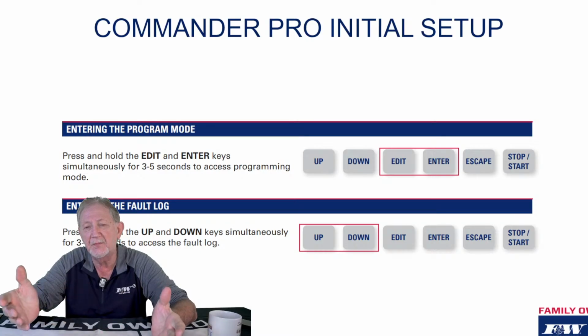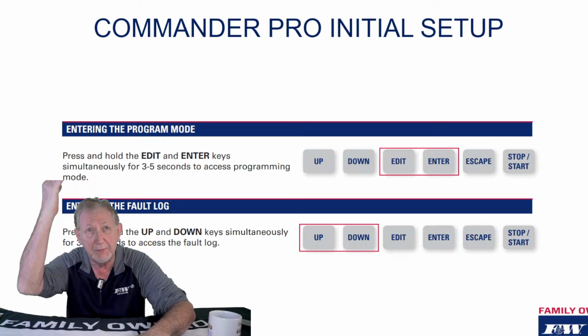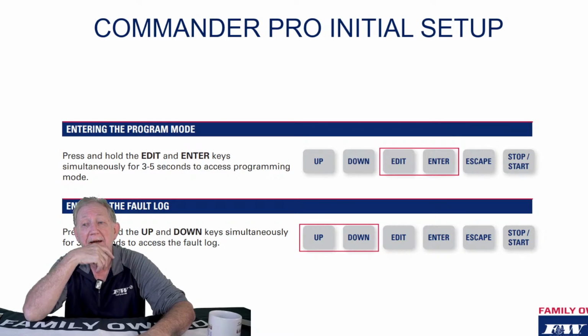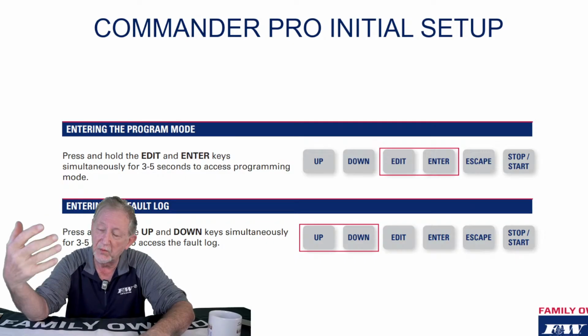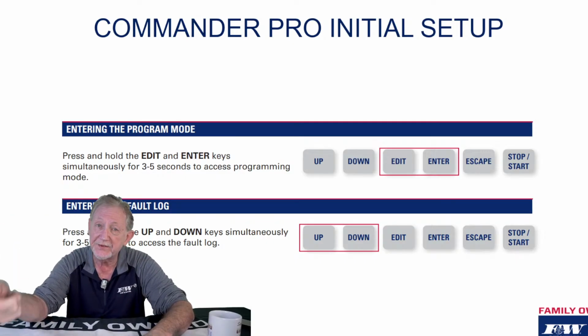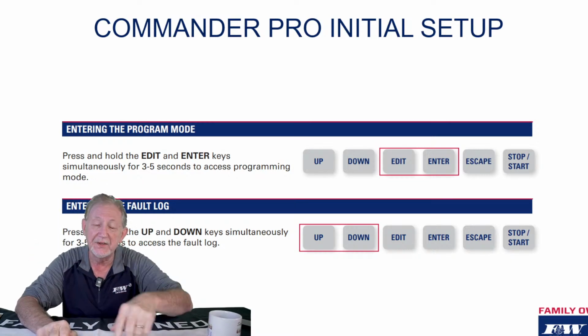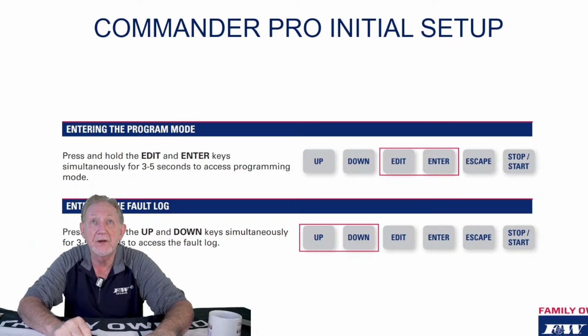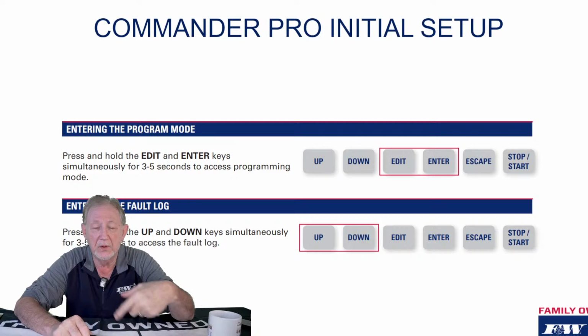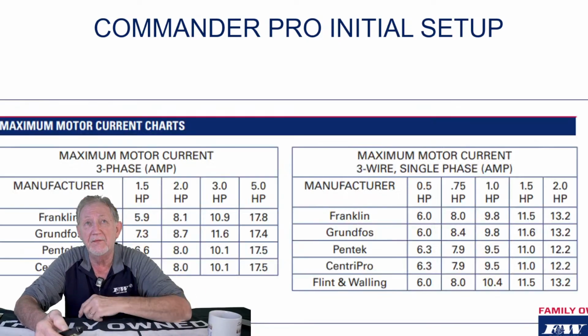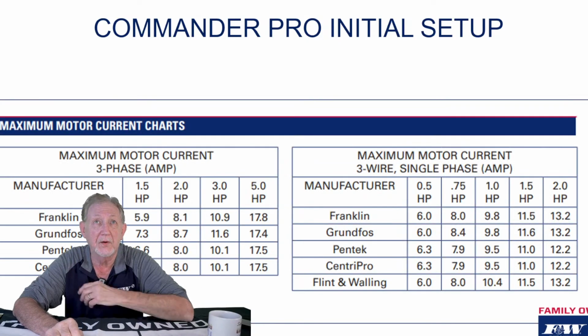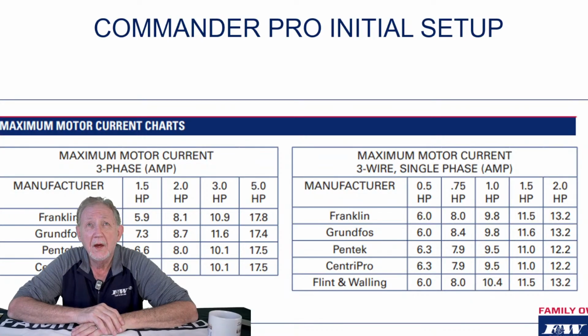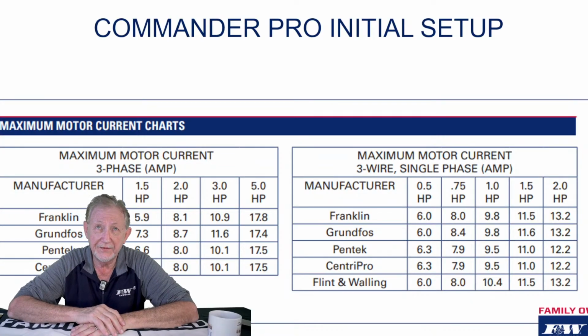So for example, if by chance you filled up all 20 of those faults, all right, so the log's full, and now all of a sudden another fault takes place. Well, what's going to happen is that fault that just took place is now going to take position number 1, and it's going to bump everybody down 1 notch, and so that means that what was in the number 20 position gets knocked off, so it goes away. But that's how that works, and that's what we're talking about when we say a revolving fault log.